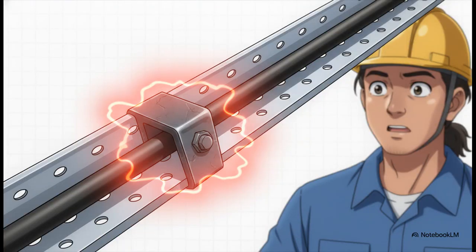Okay, here is a massive field tip straight from the code book. When you're fastening single conductors to a tray, you absolutely must take precautions to prevent overheating at the fastener locations due to induction. The physics of electricity dictate how we do our jobs, right? If you use ferrous metal clamps on single AC conductors, you're going to create a tiny magnetic field that generates heat. And over time, that heat literally destroys the insulation. Always keep induction in mind.